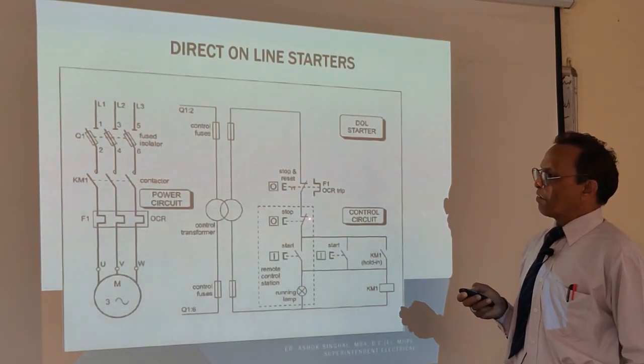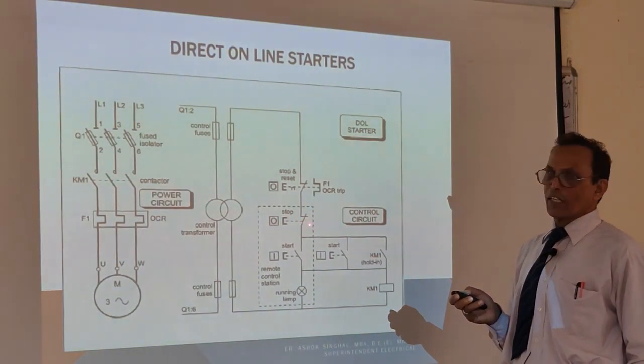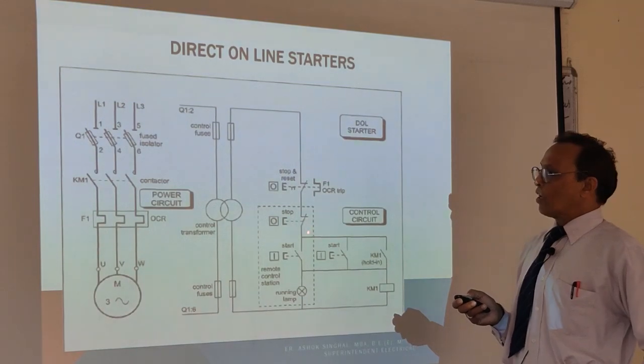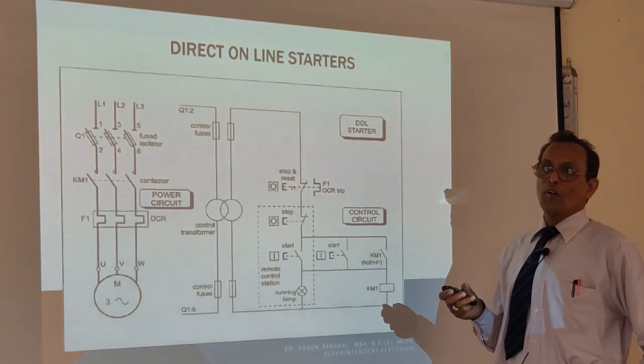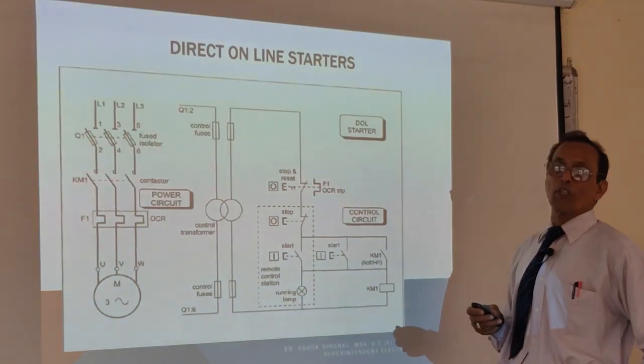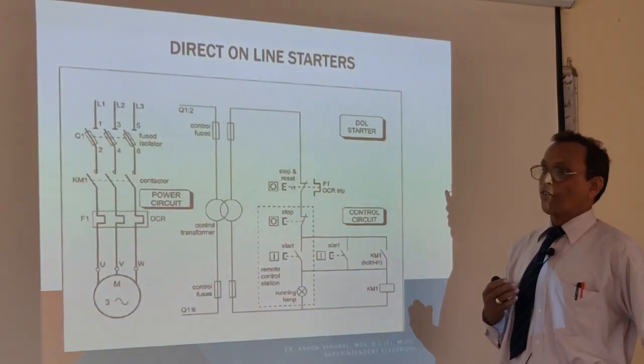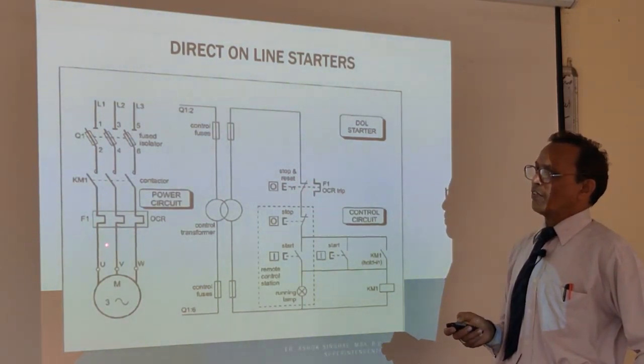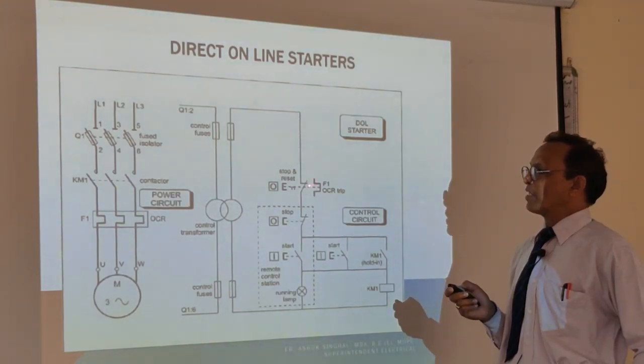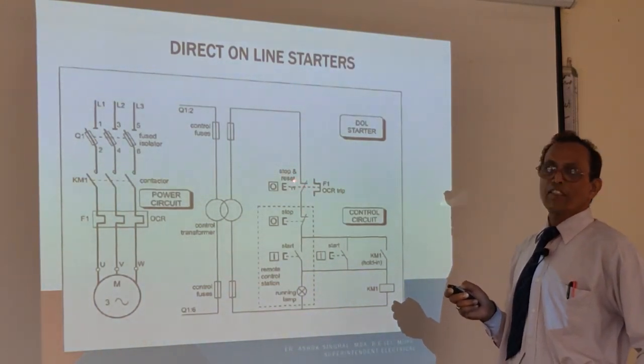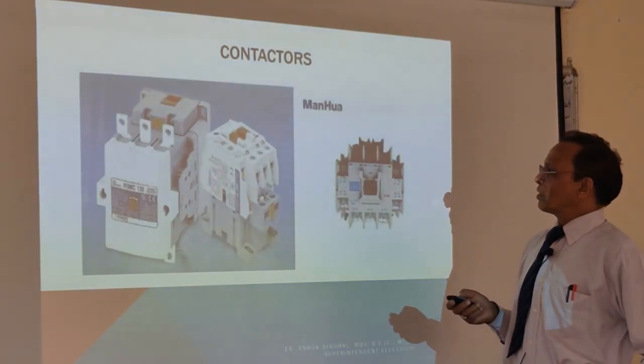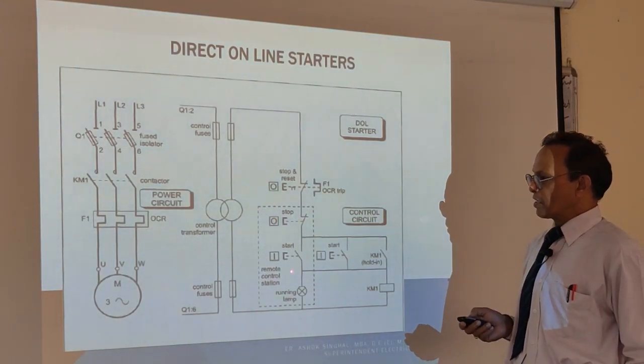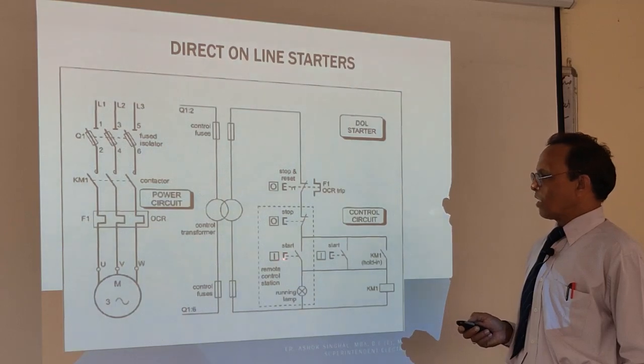For stopping, when you break the chain by pushing the stop button, you are breaking the circuit and the motor gets disconnected. For other faults — suppose you press the push button and the motor is not starting — the first thing is to check your overload relay or OCR. All three phases of 440 volts are coming, but there is an auxiliary contact F1 OCR that needs to be reset. You have two places from which you can start the motor.